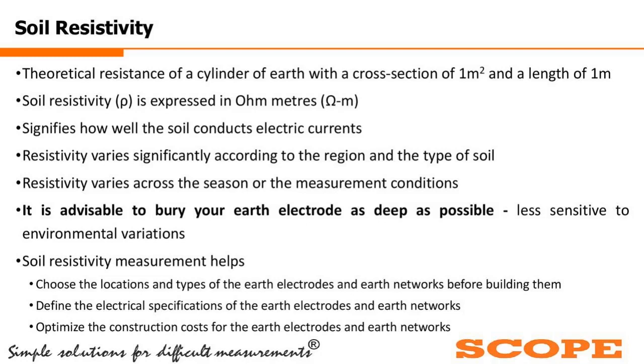Soil resistivity measurement helps us to choose the location and types of earth electrodes and earth networks before building them. Before building any factory, substation or generating station, we have to do the soil resistivity survey. We need to define the electrical specification of the earth electrodes and earth networks. What type of earthing network will I use? How big will the mesh be? How much horizontal and how much vertical strips will I use? How much depth will I use?